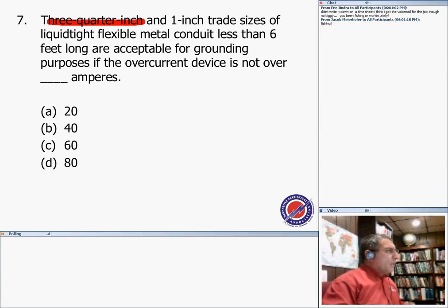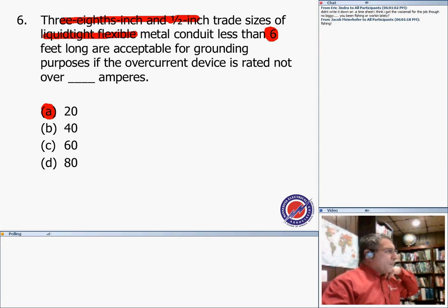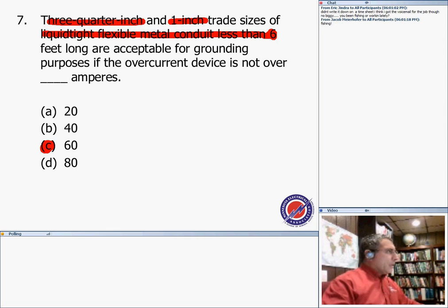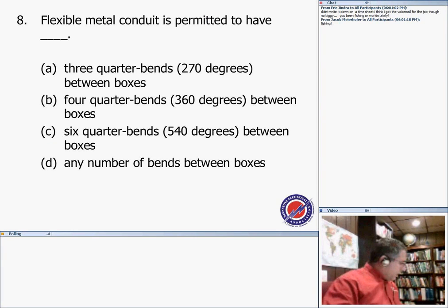The same 3/4 inch and 1 inch sizes of liquid tight metal conduit less than 6 feet. And number 7, guys, it's 60 amps, grounding conductor if there is no flexibility, and so on, up to 60 amps. So this is 3/4 inch all the way up to 1 inch. This one, 3/8 all the way to a half. If somebody's wondering why 3/8 all the way to a half, they'll limit you with the 20 amps. If you go to a bigger size, now we went from 3/4 to an inch, they allow you to go up to 60 amps on a branch circuit. Nothing needed and no vibration. Okay, now, all these have been right.